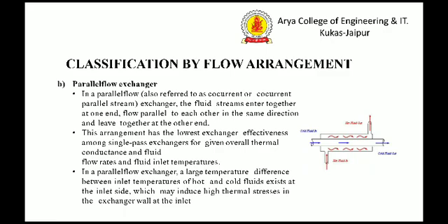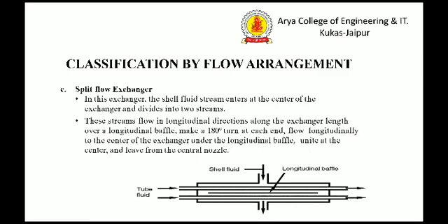In parallel flow exchanger, the fluid streams enter together at one end and flow parallel to each other in the same direction. This arrangement has the lowest exchanger effectiveness among single pass exchangers for given overall thermal conductance. In a parallel flow heat exchanger, a large temperature difference between inlet temperature of hot and cold fluid exists at the inlet side. Split flow.